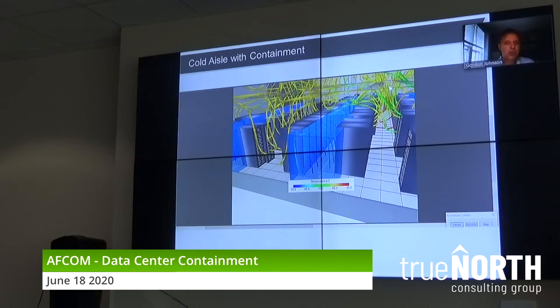Now the temperatures are in the 80s. They're very consistent, and that's been coming through the exhaust on all your racks back through your drop ceilings. So I actually lowered the temperature throughout your data center, and the reason is we got rid of net air recirculation. I'm no longer mixing cold air and hot air and pushing that through your server inlets. So that hotter temperature is causing hotter returns. Because I have consistent supply temperatures through the intakes of your servers, I have consistent return temperatures, which are actually lower than when we started.